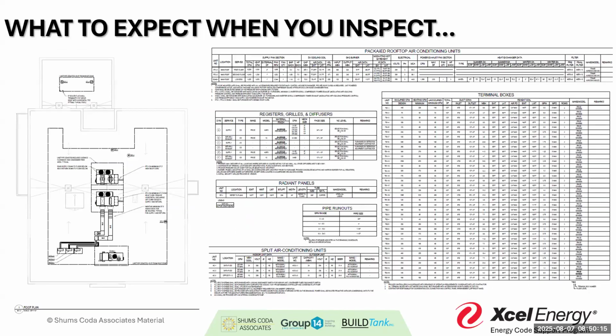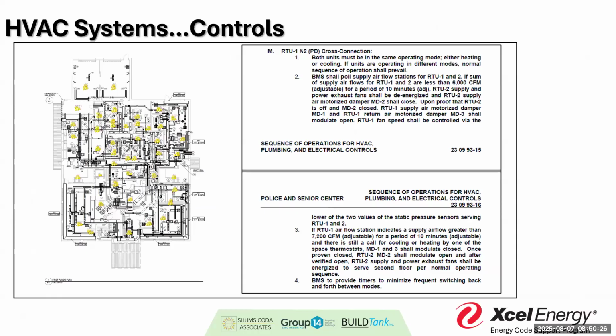So I'm going to be looking at all of those individual pieces and evaluating each one, both for mechanical ventilation and efficiency. More importantly, I'm also looking for a sequence of operations showing how this is all going to work together. This is a unique type of design for an institution that requires more than one system, so those systems need proper control balancing so we don't have, say, a rooftop forced air system working against a unit heater or a boiler heating system in an office. We want to have that level, and we kind of see that identified in some of these different calculations.